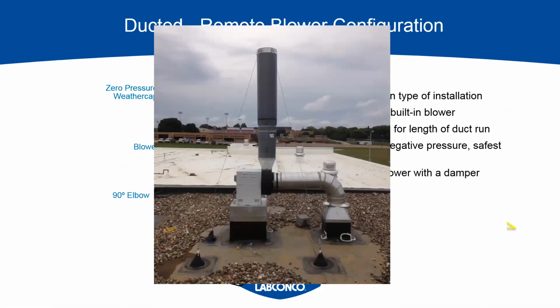So this is what a typical rooftop installation looks like with a remote blower. The ductwork goes into the inlet of the blower on the side there, and then you have the zero pressure weather cap on top to allow the air to exhaust vertically and be taken away and diluted. So this is the one hood, one blower. Obviously, it gets more sophisticated with this. If you have a bunch of different hoods, you can have a very sophisticated manifolded system, but this is just the base level to compare.